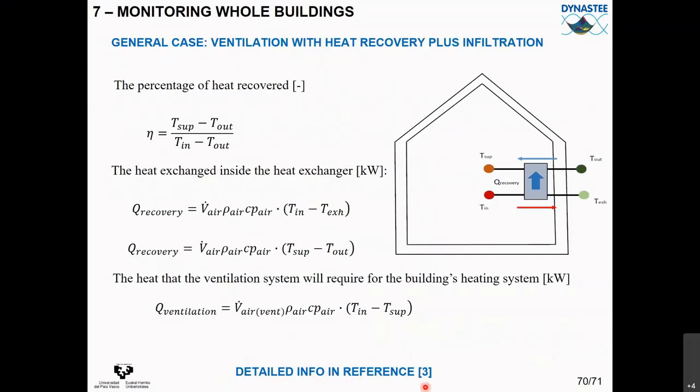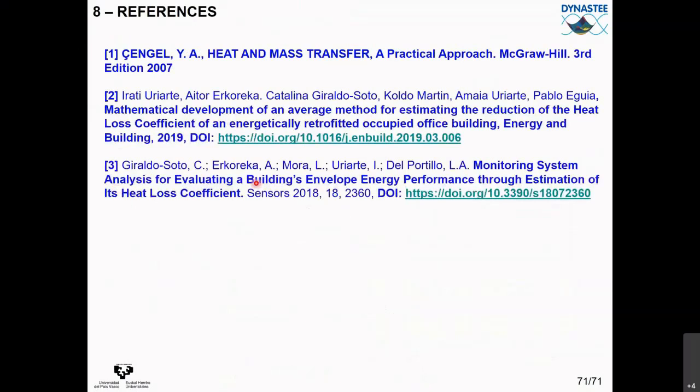Temperature, CO2, and relative humidity measurements in buildings use aesthetically suitable commercial sensors. Electricity consumption is measured with wattmeters in electrical boards, giving kilowatt-hours consumed per thermal zone. Ventilation system measurements require supply temperature, indoor temperature, outdoor temperature, exhaust temperature, and volumetric flow rates to calculate the ventilation heat loss coefficients. All information about monitoring and measuring in buildings is in the third reference provided. This presentation covered the physics of the building envelope in the first part and measurements in the second part. Three references are provided for further reading.